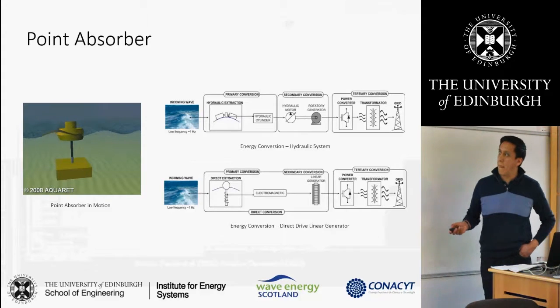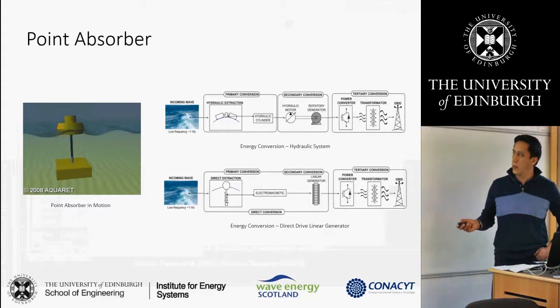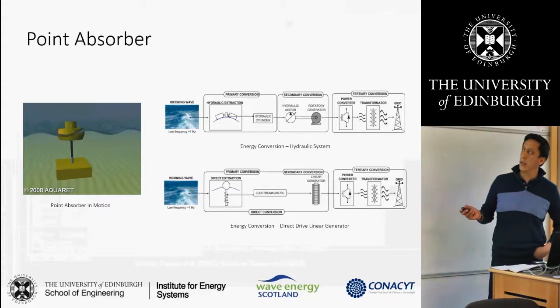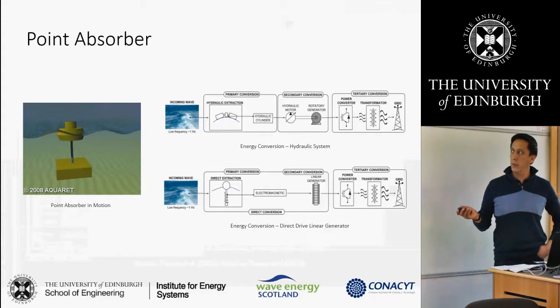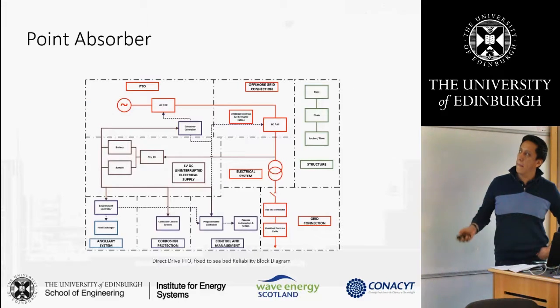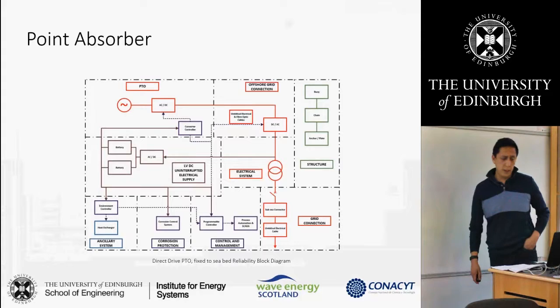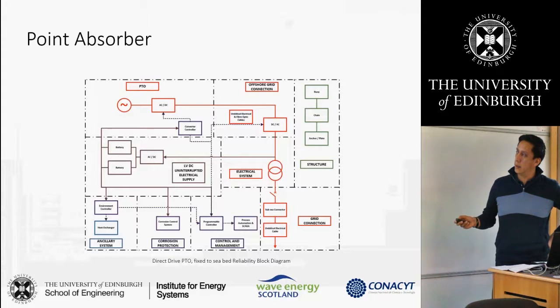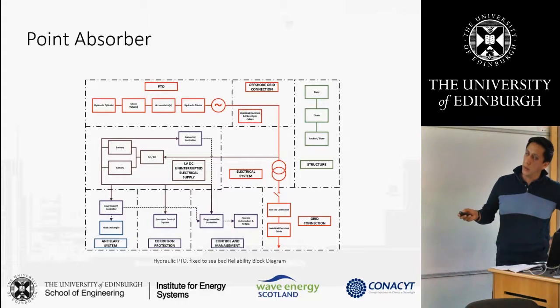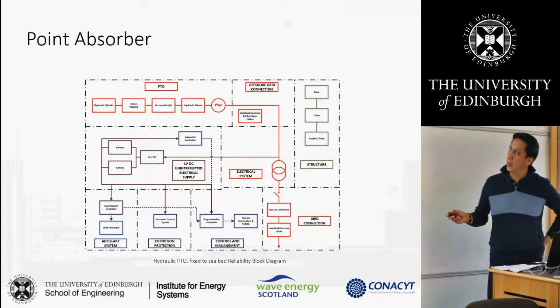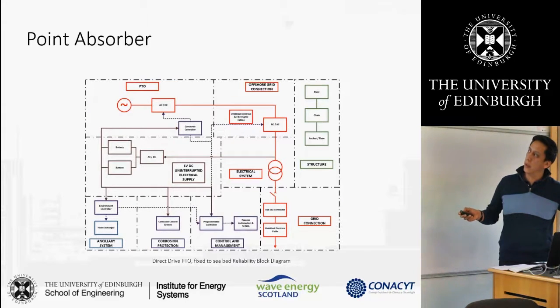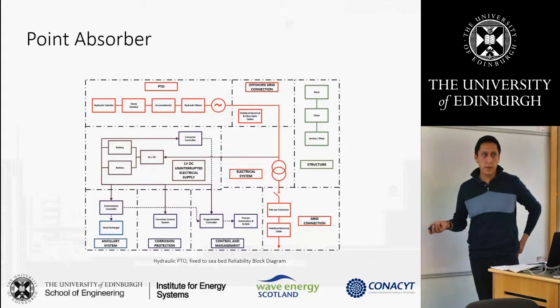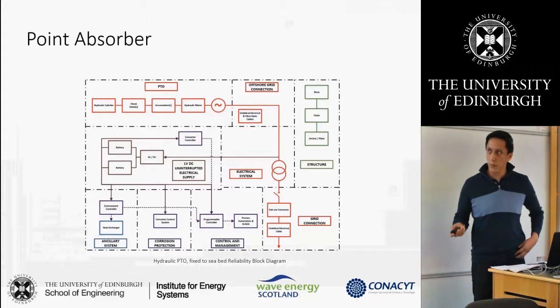For the point absorber, the power takeoff could use a direct drive linear generator, or it could use a hydraulic system. That's where the main difference lies in the point absorber, because the structure will be basically the same. A reliability block diagram for the point absorber shows the hydraulic system is more complex compared to the linear generator, so it should have a higher failure rate because it has more components.